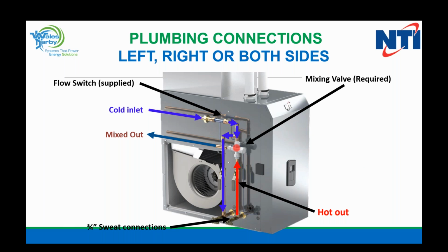So here's the mix valve. This right here is a flow switch. What that does is recognize the flow and tell the unit that there's flow going to the tankless water heater. Based on that flow switch signal, that's what will tell the tankless water heater to fire up, and it will take off and run. If you're using hot water, it's going to produce the hot water. It's going to send the hot water out.